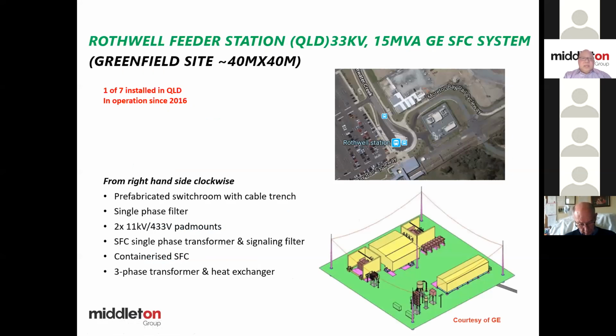Now this one has been installed in Queensland, and it is actually a greenfield site, Rothwell, by General Electric equipment. If you look at this picture here and this picture here, you can actually Google it, and you can see that the equipment only occupies about 40 meters by 40 meters. The GE version, General Electric version, they come at 15 MVA. They're rated at 15 MVA. So if you want more, you have to connect them in parallel to get higher ratings.